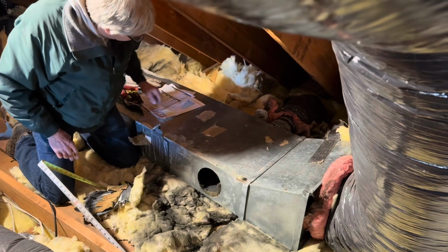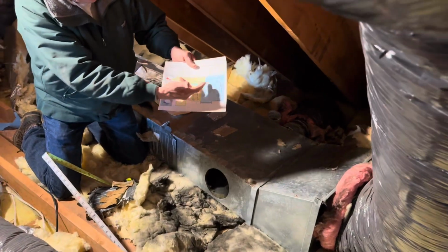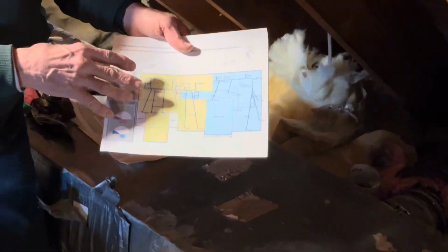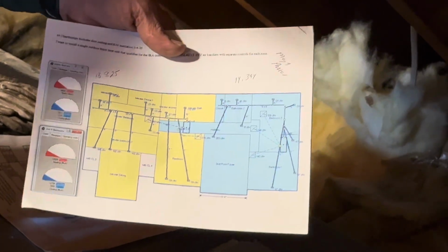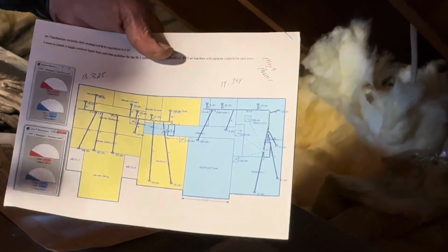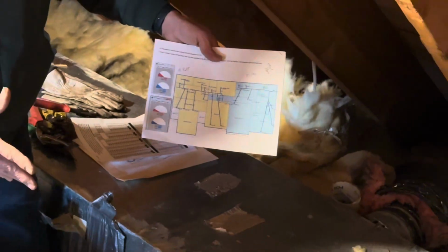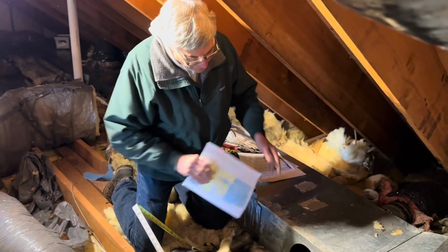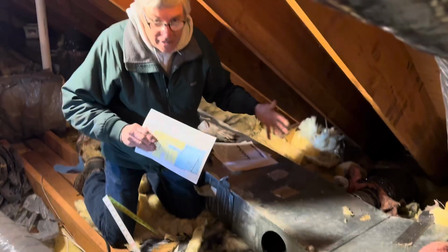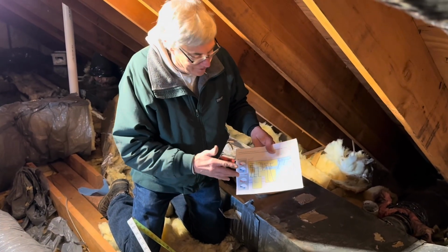Now, when somebody designed the system and put it all together on a load calculation, they would have said, okay, we're going to make an assumption about leakage, how much do we have or not. So an unlined duct leaks a lot, and it needs to be a larger size. A lined duct needs to be a larger size because we put a liner in and reduce the interior. And so that all needs to be taken into consideration.